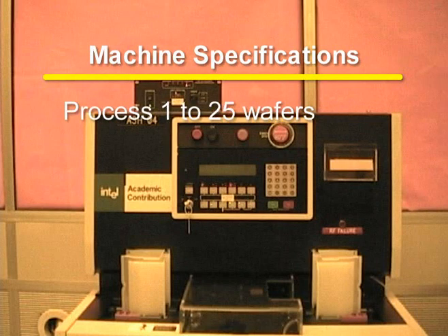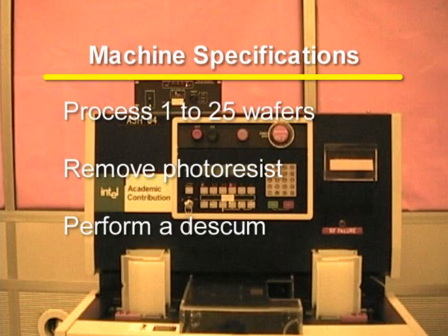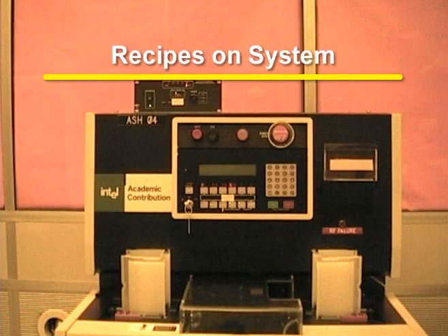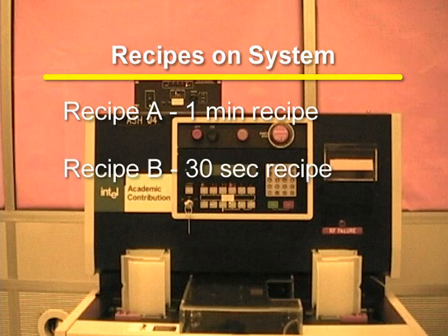The Gasonics Asher can process 1 to 25 4-inch wafers during a run. The Asher can either remove the photoresist from the wafer or do a de-scum on the wafer. There are currently two recipes on the system. Recipe A is a one-minute recipe used to remove up to 1 micron of photoresist. Shipley 1813 photoresist was used to test the removal rate. Recipe B is a 30-second recipe used for a de-scumming process.